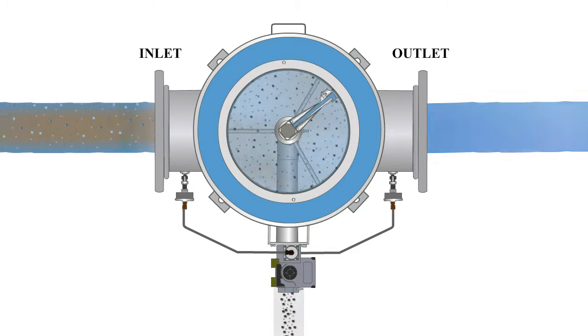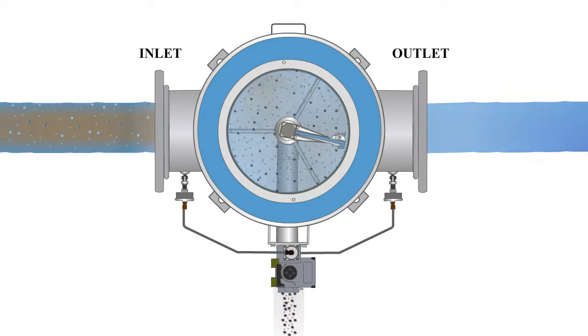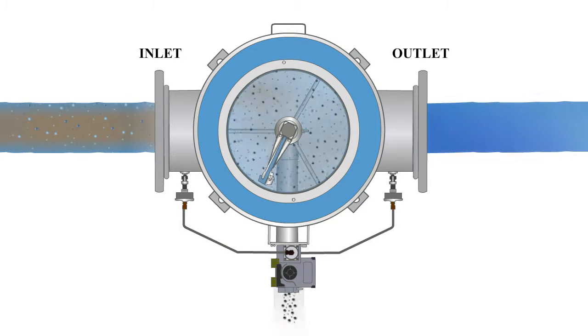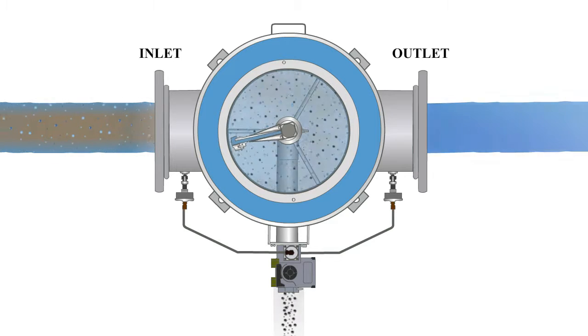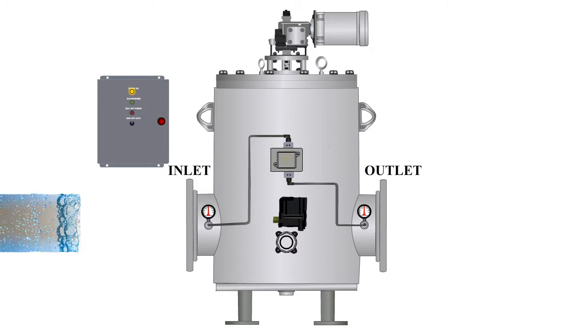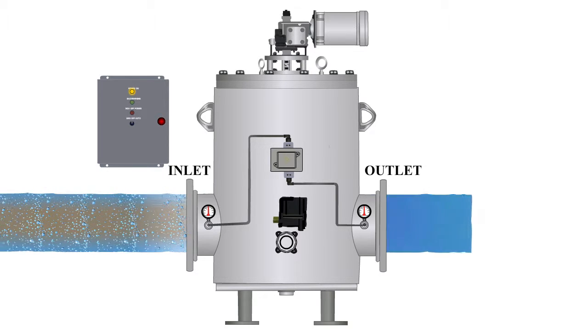If the strainer sees a sudden high debris loading, the differential pressure switch can also trigger a backwash sequence. The differential pressure switch measures the pressure between the inlet and outlet of the strainer.